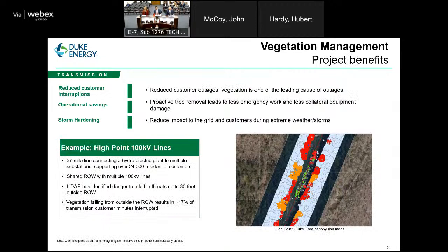But what we do is we perform aerial inspections of our transmission system on a regular basis. And we use a technology called LiDAR to scan these transmission lines. And what we're doing is we're looking for these hazard trees outside of the right-of-way. So in the image on the right here, you can see in the middle of the right-of-way is the transmission circuit. And this is actually our high point 100 kV circuit. It's a dual circuit line, so there's two lines actually running down this right-of-way. On the right and the left side, you can see the orange and red polygons. And these are created by our scanning software. Anywhere there's a colored polygon, we have a hazard that needs to be assessed.